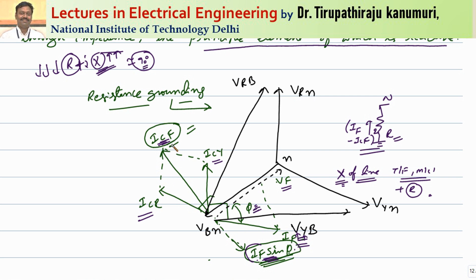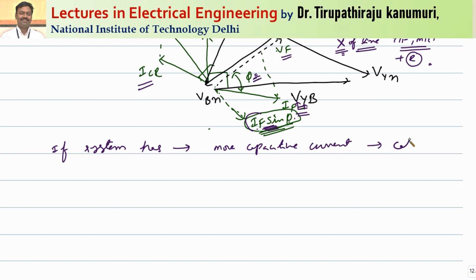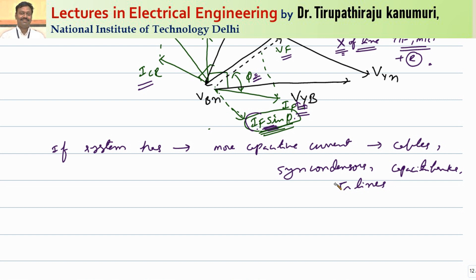If the system has more capacitive components — for example cables, synchronous condensers, capacitor banks, or transmission lines without transformers — the capacitive currents will be dominating. When capacitive currents are more, the value of IF sin phi required will be more, so automatically the fault current required will be more, and hence more losses will be there in the resistor.